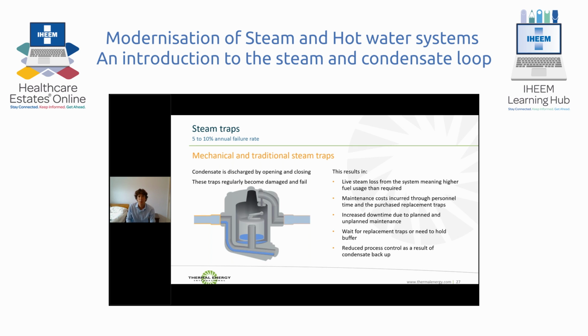Some operate on temperature, opening and closing on temperature. Others operate on density with various float mechanisms. This one here is an inverted bucket trap, which again is a density trap. Effectively, you have a bucket that moves up and down when steam and condensate is present. We also have thermodynamic types of steam traps, where the trap opens and closes based on the difference in flow velocity between steam and water through the device.